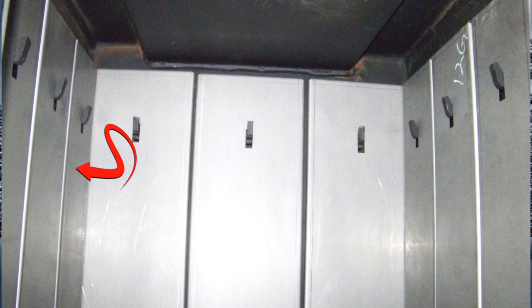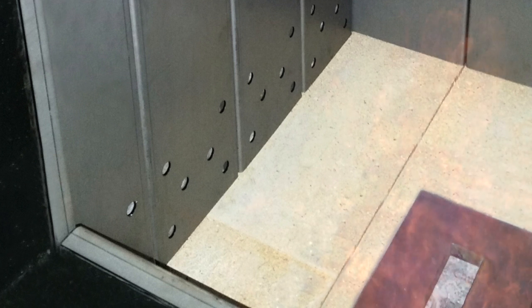Looking a little deeper into the firebox, you will notice that all four sides are protected with mild steel air curtains. The curtains are actually removable for cleaning, repairing or replacement, all the while protecting the fire chamber from damage and corrosion. On the base of the firebox, you will find more refractory cement than any other furnace of its size on the market today. This refractory cement allows the firebox to remain dry and eliminates ash-line corrosion. It retains incredible amounts of heat, which end up heating the water in the EGR's water jacket via the eight horizontal heat exchanger tubes and an additional eight vertical heat exchanger tubes, heating the water and not up the stack like other wood furnaces.